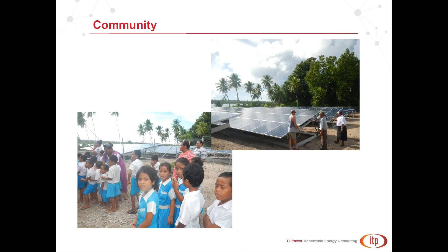So finally, just some lessons from the project, quickly, since we're going over time. One risk with these systems is they become too reliable, meaning operators stop maintaining the generators because they don't need to run them regularly, and become complacent. Then when the generators are needed, they're not available, which can lead to system problems or over-discharge of the batteries.